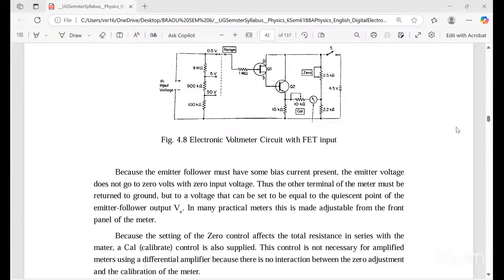In many practical meters, this is made adjustable from the zero control point. The setting of the zero control affects the total resistance in series with the meter, and a calibration control is also supplied. This is not necessary for an amplified meter using a differential amplifier, because there is no interaction between the zero adjustment and the calibration.